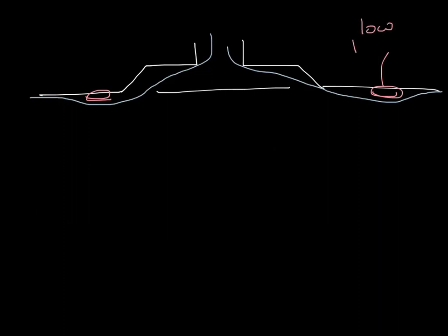In the ceiling dependent versus ceiling independent podcast, I discussed that the ceiling dependent diffuser needs a ceiling to create this low pressure zone. So let's start with that. This is a ceiling dependent diffuser. The supply air jet comes out the inlet, and as it leaves the diffuser face, a low pressure zone is created and it's pulled back up towards the ceiling. This low pressure zone is pulling the air towards the ceiling, and that's how a ceiling dependent diffuser holds its air pattern. It's dependent on the ceiling. This low pressure zone is often where you'll see the smudging on the ceiling tiles just outside the diffuser face.